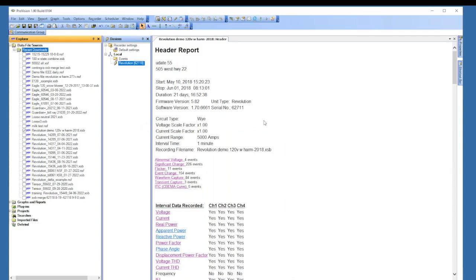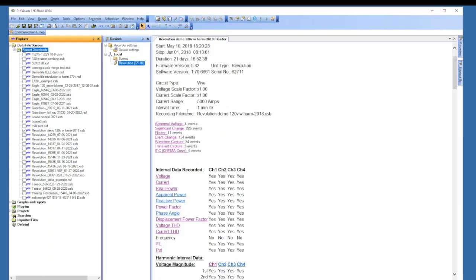Now the header report shows how the recording was set up. So you can see we have a start and stop time, when it was put on power and was taken off of power, how many days, some information about when it was recorded. Interval time. The Revolution samples at 16,666 samples per cycle. The Eagle samples at 256 samples per cycle. The interval time is what your graphs look like. So if you have a 1 minute interval, every 1 minute will be plotted in your graph with the lowest cycle during that 1 minute, the highest cycle during that 1 minute, and then it'll take all those hundreds of thousands of samples and give you an average for that 1 minute.